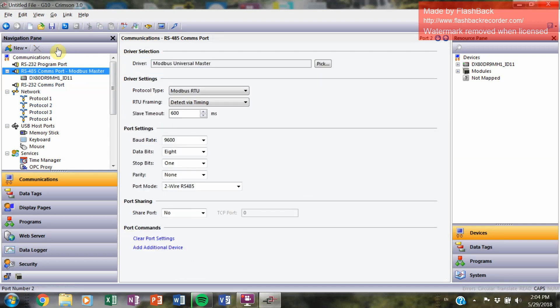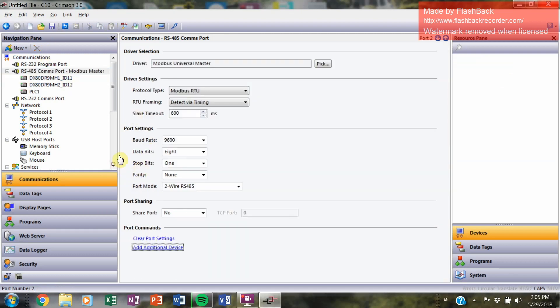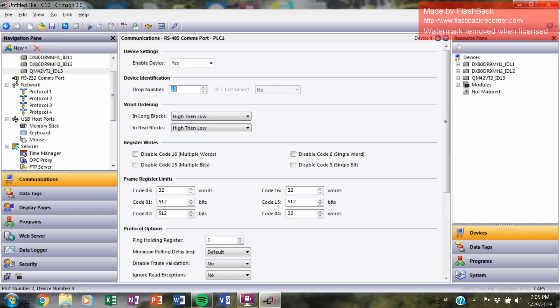We're going to do this for every device we have connected. Go back to the comm support, scroll down to Add Additional Device, and it'll give you another block. Give it a name — in this case, DX80DR9MH2 underscore ID12 — and update the drop number to 12. Then let's add the rest of the devices. My third device is the vibration sensor, a QM42VT2, which is slave ID number 13. We'll change the drop number to 13.